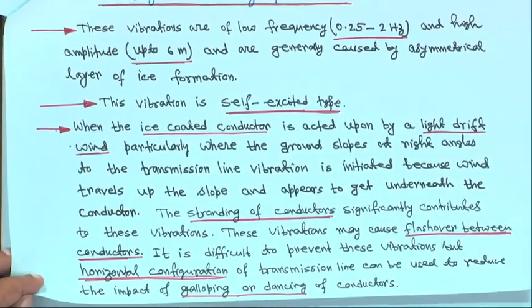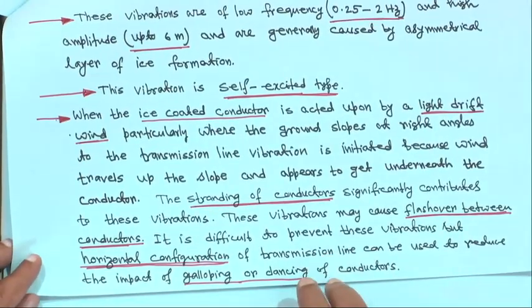This vibration may cause flash over between conductors if they are in vertical configuration. It is difficult to prevent this vibration, but horizontal configuration of transmission line can be used to reduce the impact of galloping or dancing of conductor. In hilly areas, horizontal configuration of conductors is preferable over vertical spacing. With this, the sag and tension chapter is complete. Go through all the derivations, particularly for towers at different heights, ice formation, and wind pressure. Thank you, we will be back again.